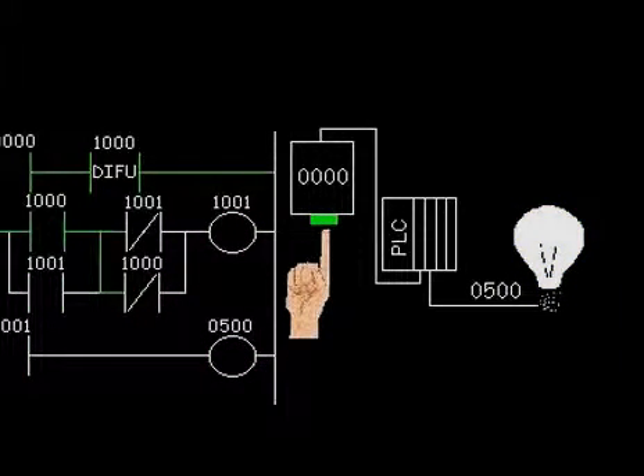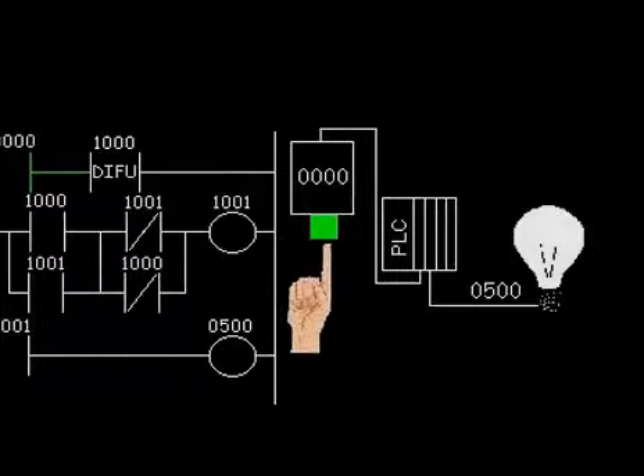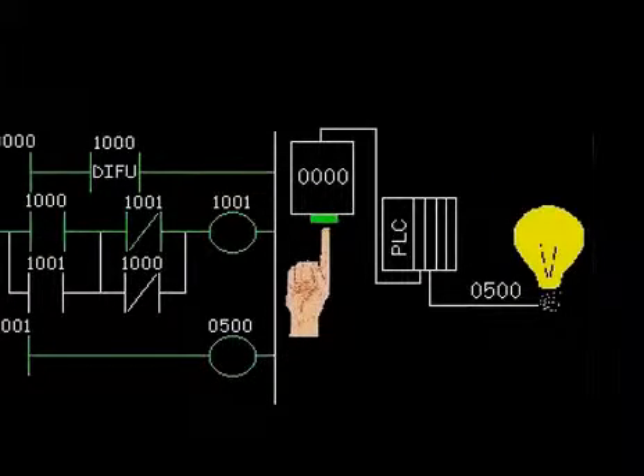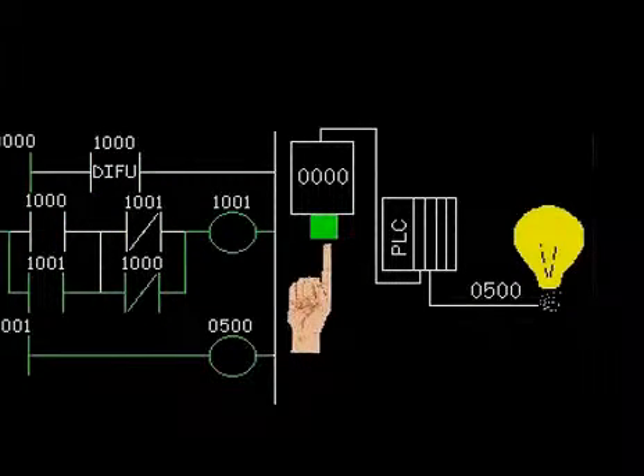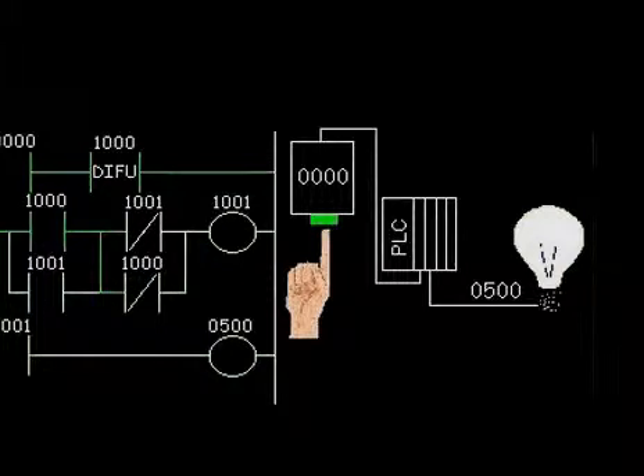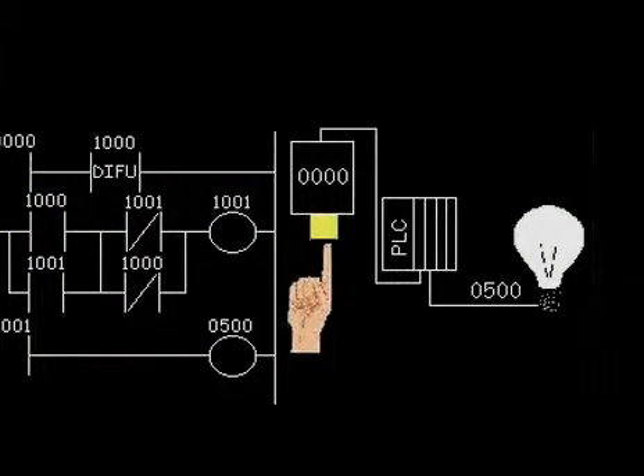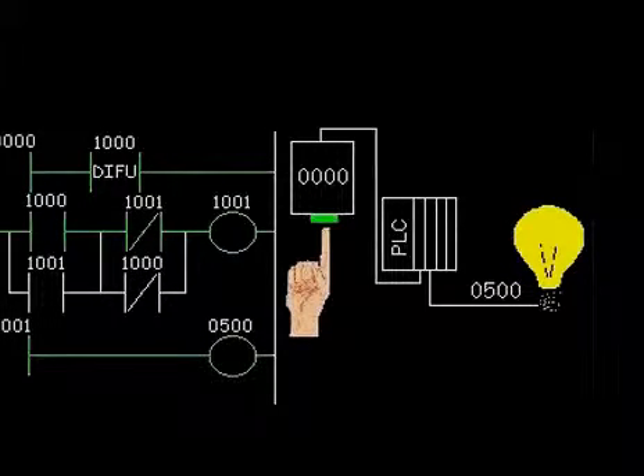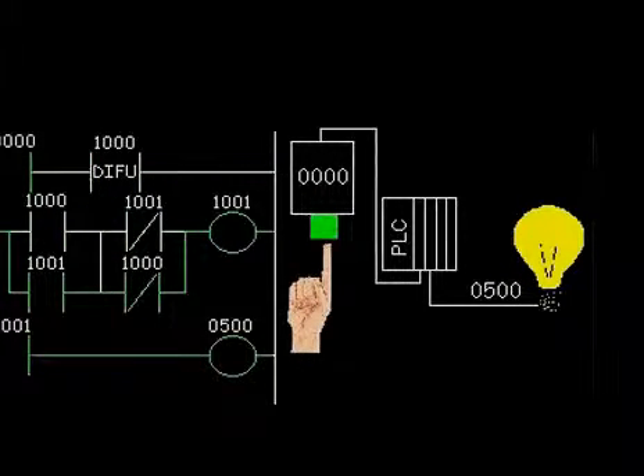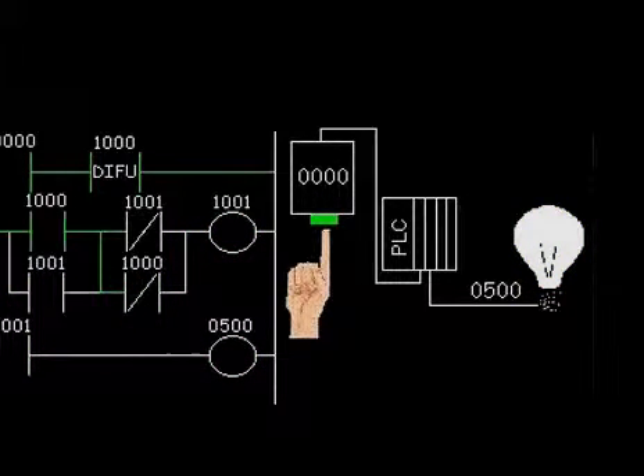One of the advantages of implementing logical control in software rather than in hardware is that input signals can be reused as many times in the program as is necessary. Using a PLC, we can program as many contacts as we wish for each input without adding additional hardware, since each input and each output is nothing more than a single bit in the PLC's digital memory, either 0 or 1, and can be recalled as many times as necessary.